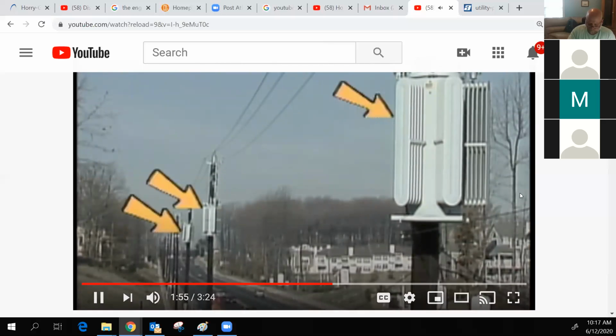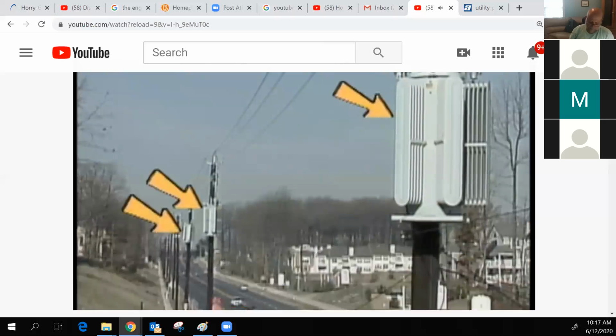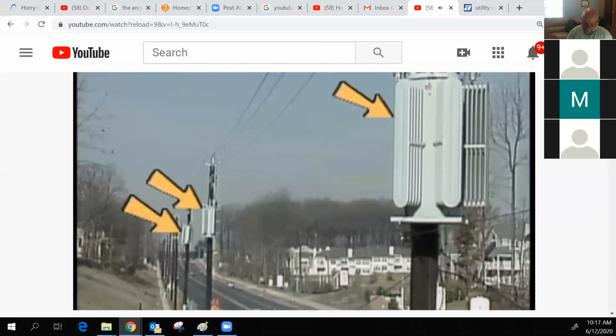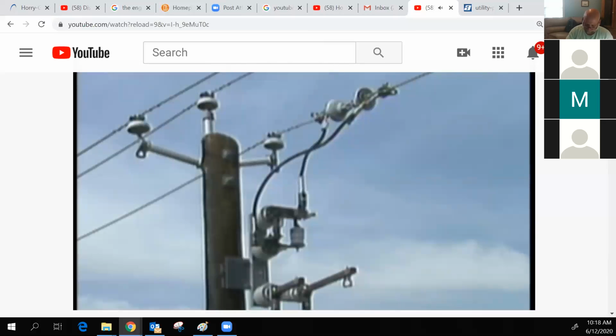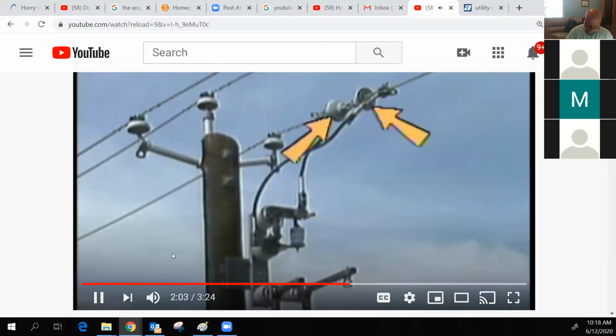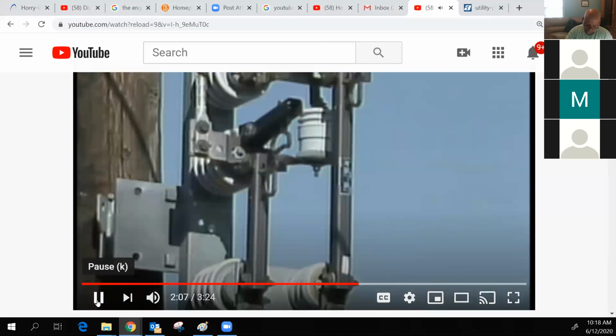Here, the voltage regulators for each phase have been mounted on separate poles. The phase is broken by inline insulators at the pole, and the regulator is connected to each side of the phase through a pair of permanently mounted disconnect switches and a bypass switch. In this case, the switches are mounted on a common base. However, other methods of connecting a regulator to the system may be used.